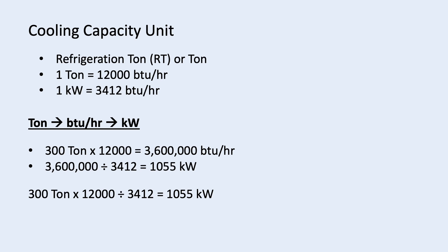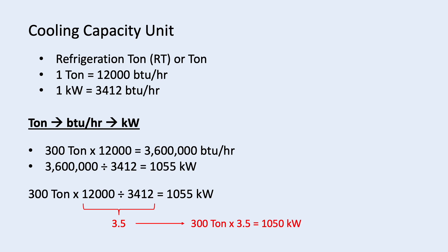However, there is a faster way to do it. 12,000 divided by 3412 is around 3.5. So, you can straight away multiply 300 by 3.5 to get 1050 kilowatt.